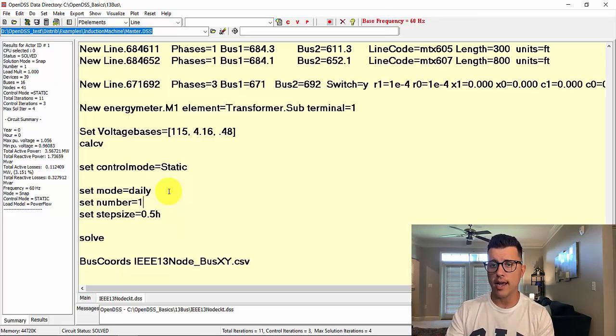I can even say I want 48 and 1 hour, so I'm going to simulate 2 days actually. The only thing I want to mention here is that if you have a load shape of 24 points, each hour, so you have a 24 hour load shape, and you simulate 2 days, OpenDSS will just loop your load shape twice. That's what's going to happen.